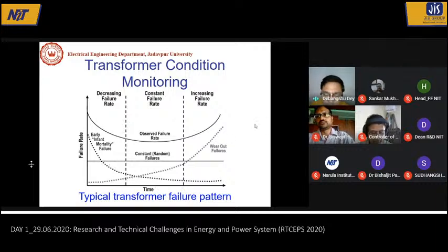If you have a large number of transformers and plot the overall failure rate, the combination of these two curves gives the bathtub curve. In the middle region the failure rate is low, but over time it increases. Most of our power infrastructure and transformers are now almost at the edge of their designed life, so they have reached that third portion where the failure rate increases.